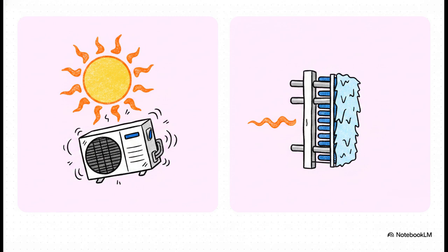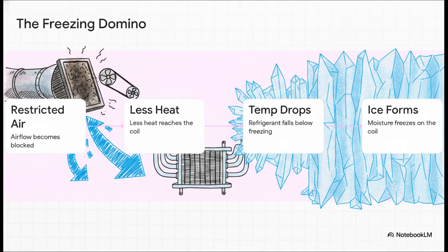But the counterintuitive reality, an evaporator coil actually freezes because it's not receiving enough heat. The refrigerant inside is specifically designed to absorb heat from the air passing over it. And this brilliantly illustrates what I like to call the freezing domino effect. So when airflow gets restricted, say by a ridiculously dirty filter or maybe a slipping fan belt, less heat actually reaches the coil. That causes the refrigerant temperature inside the tubes to plummet well below freezing. As a result, the natural moisture just hovering in the air literally freezes right onto the coil's cold surface. And once that ice starts building, well, airflow gets even worse, temperatures drop further, and the problem just feeds on itself until you've got a solid, impenetrable wall of ice.